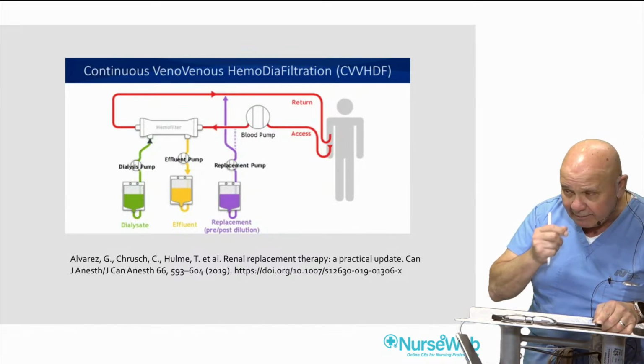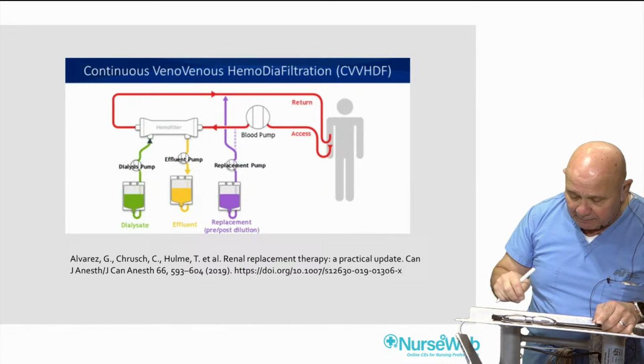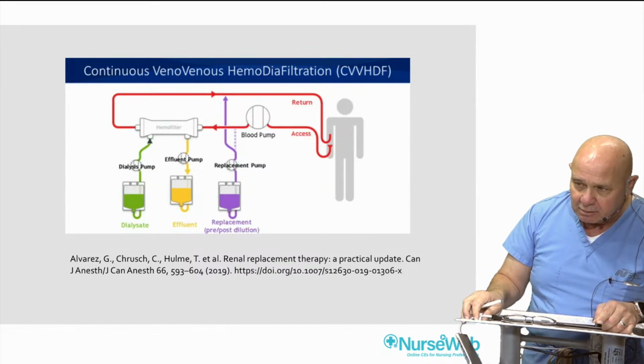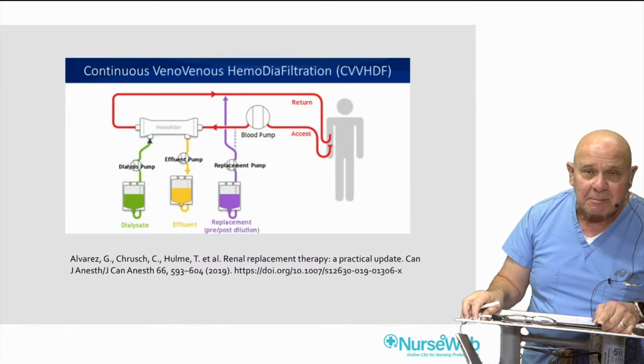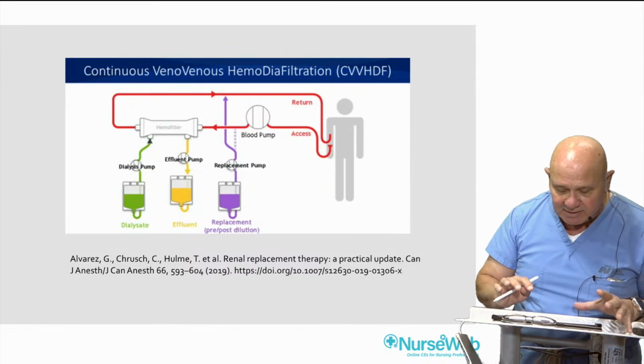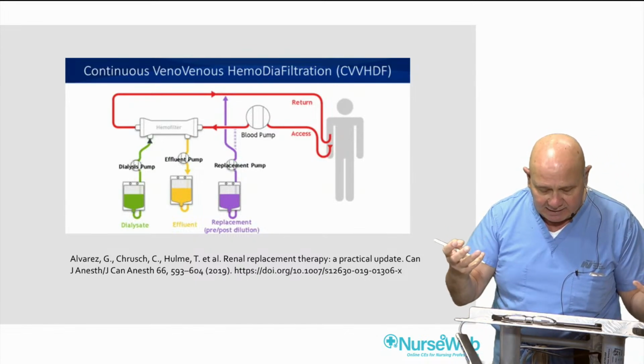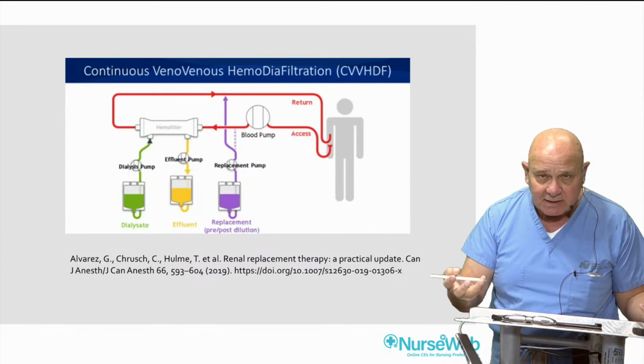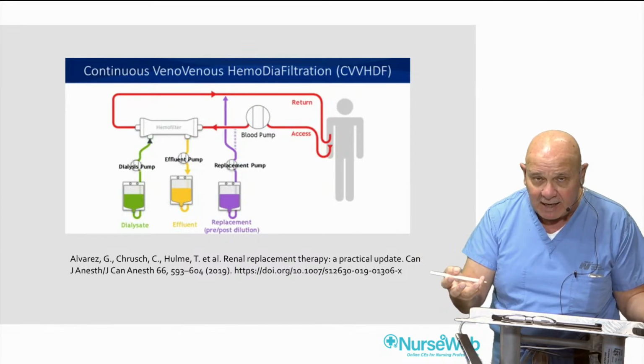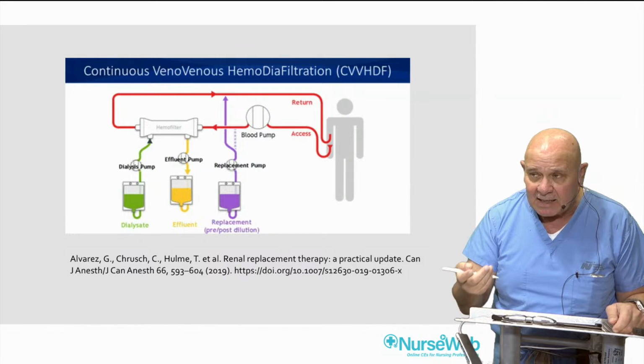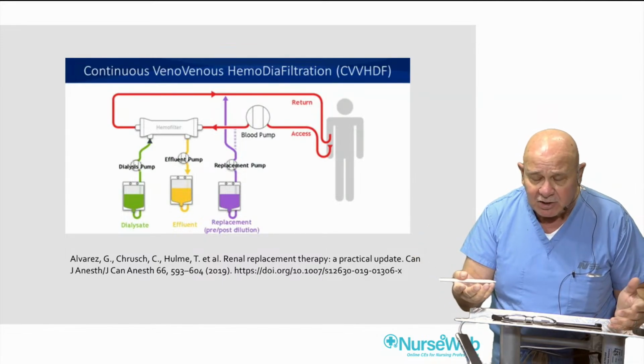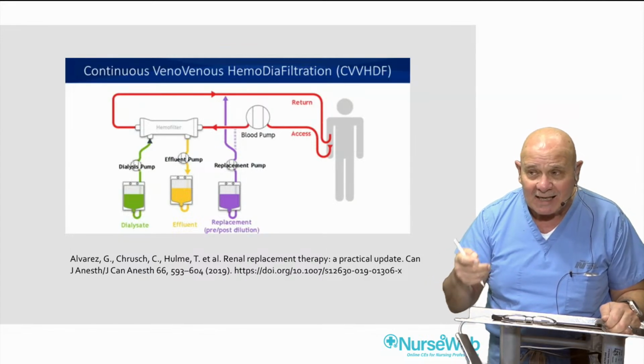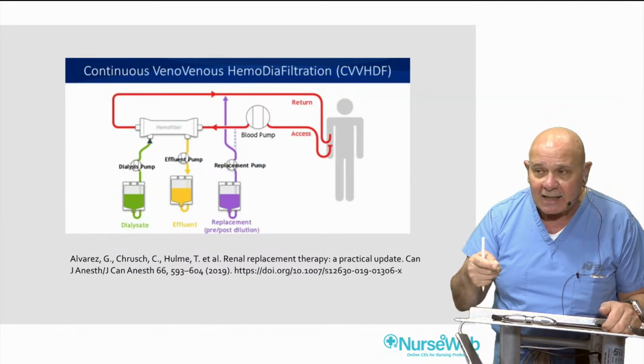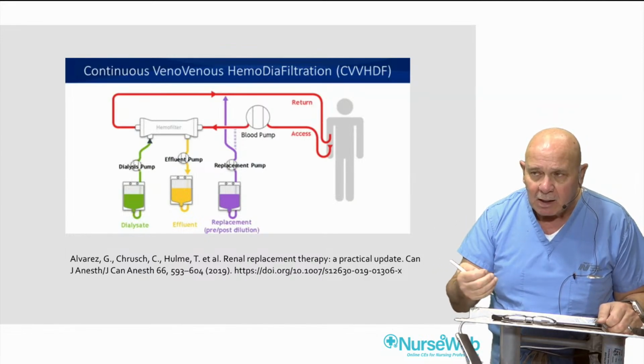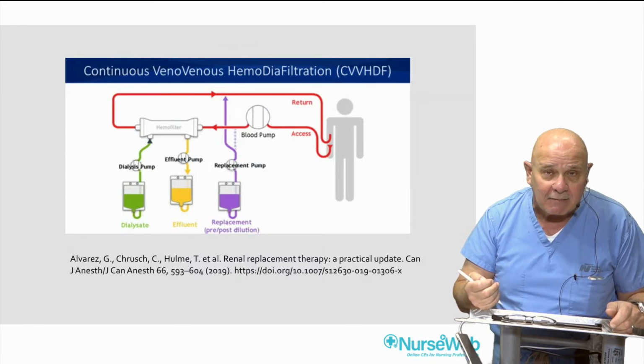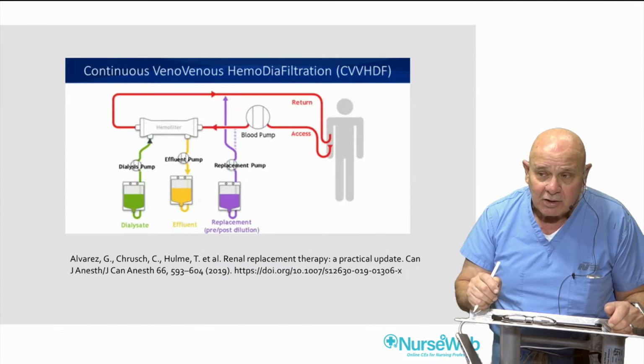Again, it's my opinion, I think that the Baxter, Gambro, Prismaflex, or Prismax are the better of the widgets at doing this. They are gravimetric, which means that they weigh the bags, and they have really sensitive scales. Now, that can be sometimes a pain in the neck, but it's very accurate, whereas a system like the NxStage, which is not a bad system, I just don't prefer it, is volumetric, meaning it's counting revolutions of a pump head, and it is computing from that the volume. And that, of course, can have inherent inaccuracies. If you're a perfusionist, I think you inherently understand that.